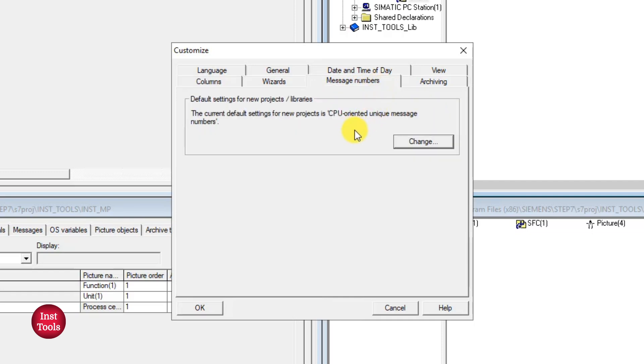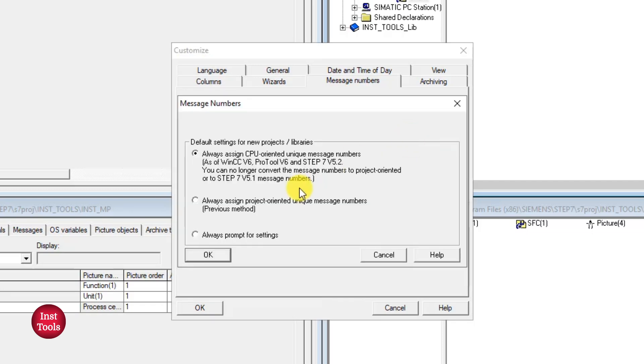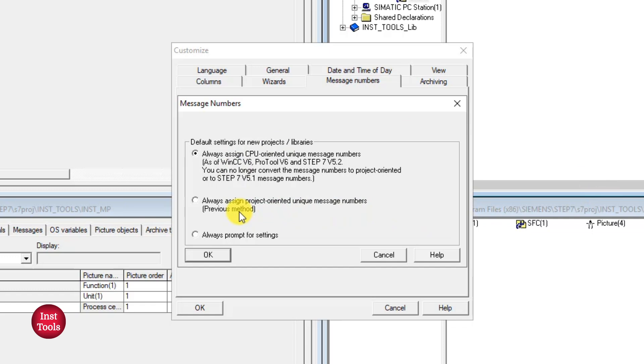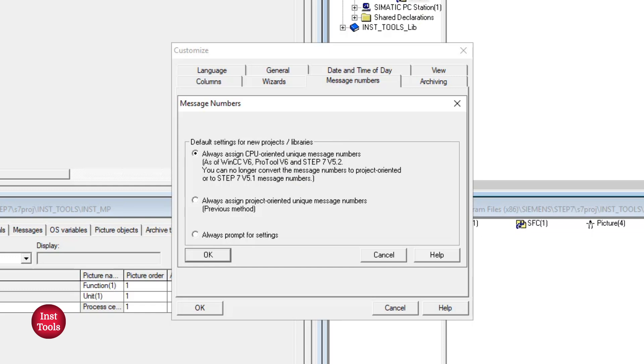And next, message numbering. So basically in PCS7, whatever the messages we are creating in CFC area or logical area or alarms, those things will be defaultly given some number to communicate to OS. Previously the mode was unique when user need to provide project oriented unique messaging numbers. So we will be given unique number. And after few years it was adapted with CPU oriented unique messages. So whenever we are creating a CPU in our user project, automatically it will create its messaging numbers. So it will be communicated to the OS. So you can choose any of these two options or you can always prompt for setting while creating user project.